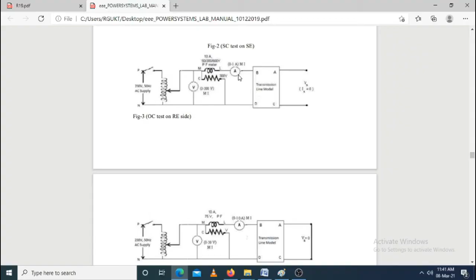We are applying the rated voltage, 0 to 300 volts, and measuring with the ammeter, so that voltage divided by current is the impedance. Similarly, at the receiving end side, we apply the rated current with the sending end short circuited. Rated current is 5 amps, applied with the help of the auto transformer. The voltmeter reads the short circuit voltage, and short circuit voltage divided by short circuit current is the impedance. ZRS means the receiving end impedance at short circuit condition. So we have calculated ZSO, ZSS, ZRO and ZRS.